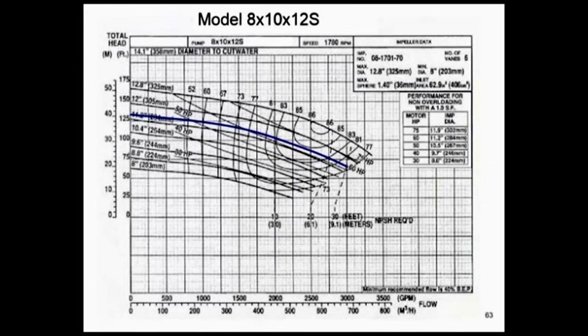So first of all, when you buy a pump, you're going to get one size impeller. Yeah, I can change the speed of the pump, which we can talk about later, and in effect change the size of the impeller. But once I have a specific speed going, whatever the speed may be, I'm going to have one impeller size. And that one impeller size is where you buy it from the factory. In this case, we have a little blue line. I think the impeller size is a little bit over 11.2 inches or something like that. And I think you see that it's been picked for 2,200 GPM at 100 feet of head. It's been a point we picked it for.